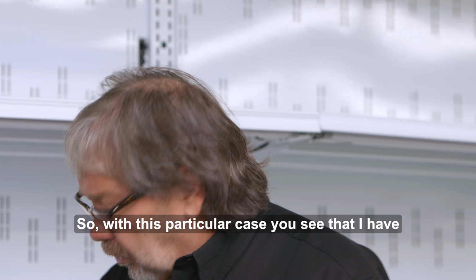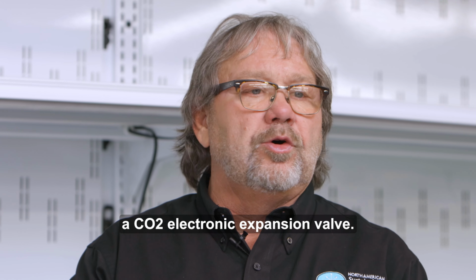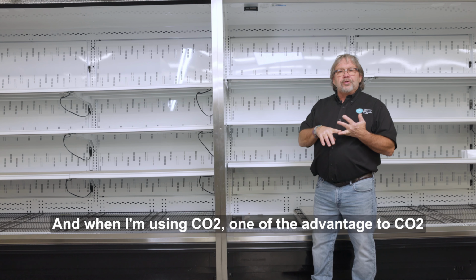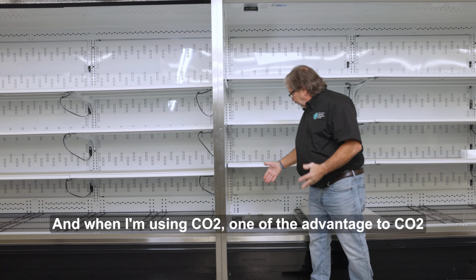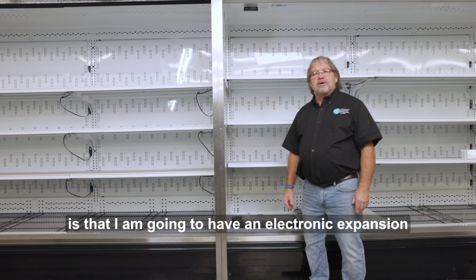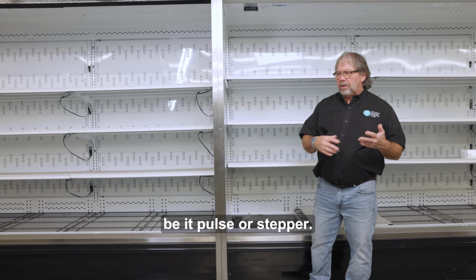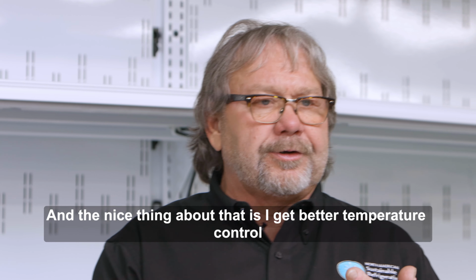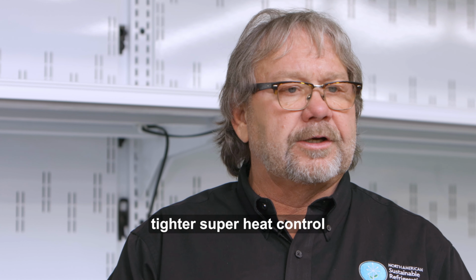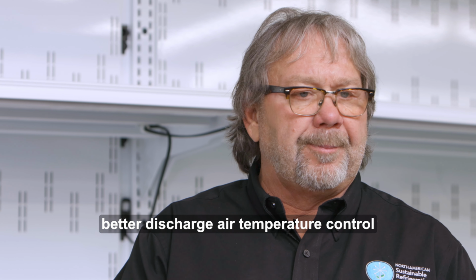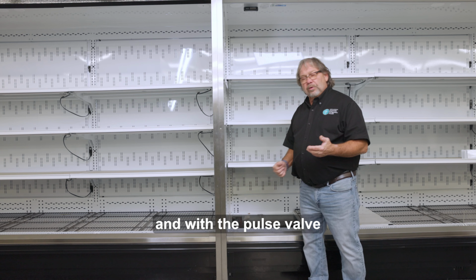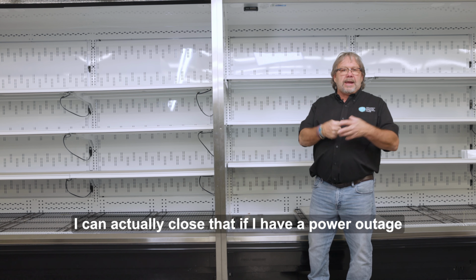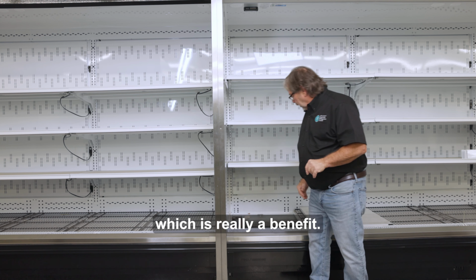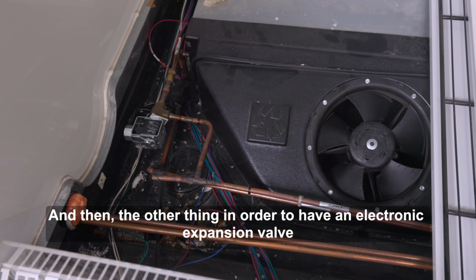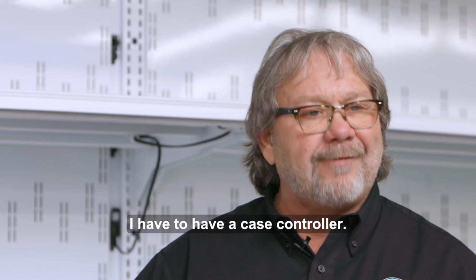So with this particular case, you see that I have a CO2 electronic expansion valve. And when I'm using CO2, one of the advantages is that I am going to have an electronic expansion valve, pulse or stepper. And the nice thing about that is I get better temperature control, tighter superheat control, better discharge air temperature control, and with the pulse valve, I can actually close that if I have a power outage, which is really a benefit.